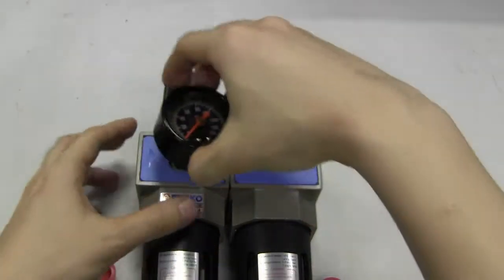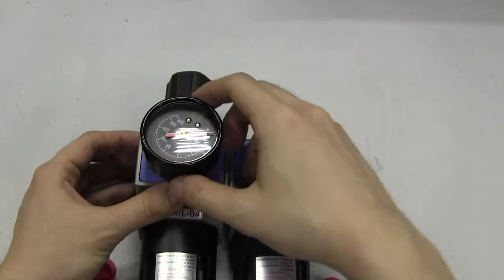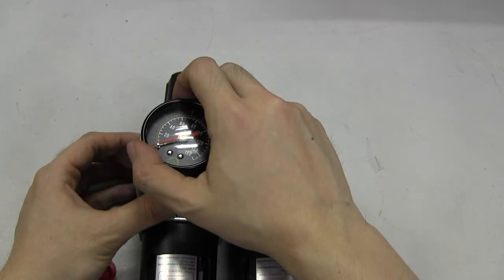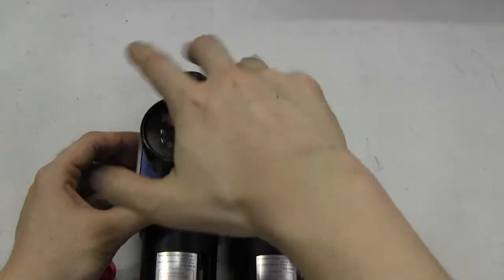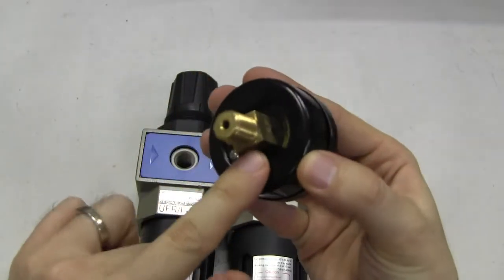When you're going to install the pressure gauge, make sure you put Teflon tape first. You can hand tighten that at first, but for the final tightening do not use your hands. Use an open wrench to tighten. I think this is a 14mm wrench that you're going to use.